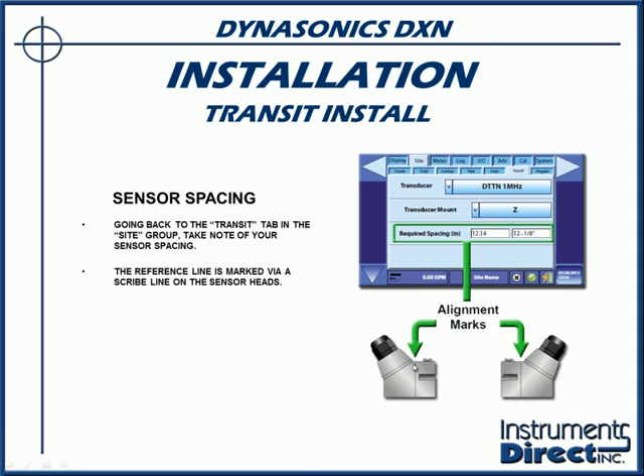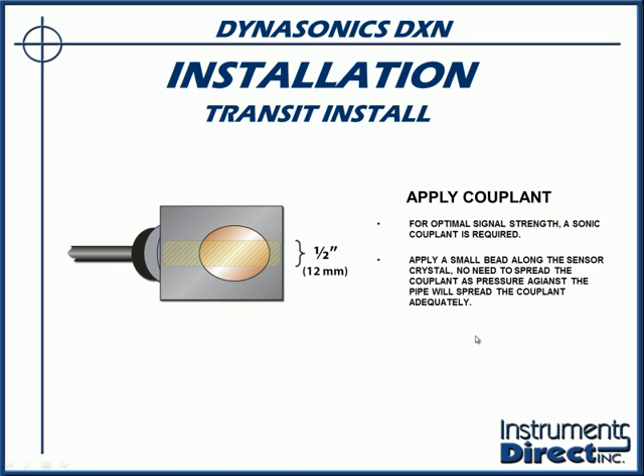It is actually from this scribe line to this scribe line. So that's the differential points of an ultrasonic transit time flow meter. And note the transit time flow meter transducers, the cable outputs go in opposite directions as opposed to the Doppler transducers. So we go ahead and we got the spacing for our ultrasonic transit time flow meters.